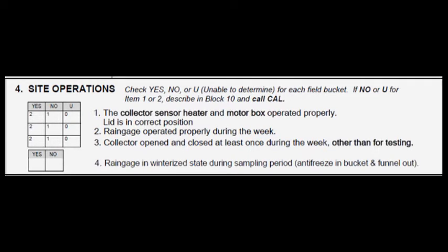Once this is done, record any additional information needed to complete Block 4, Site Operations, on the field form. In this block, you'll need to check either the Yes, No, or Unsure column for each of the first three items. Item 1 asks you to verify that the collector's sensor and motor box operated properly and that the lid is in the correct position — this should have been determined when you first activated the collector. Item 2 asks you to verify that the rain gauge operated properly during the week, determined by referring to your Belfort or electronic rain gauge chart. Item 3 asks you to verify if the collector opened and closed at least once during the sampling period, other than for testing purposes. Finally, don't forget to indicate in Item 4 whether or not your rain gauge was in winter operation mode during the sampling period.